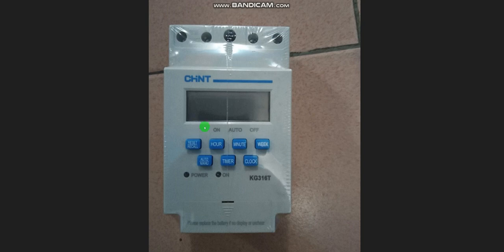It's a calendar timer. You can say, okay, every Monday, this gen can come up. Monday till Friday, gen 1 can work, then another Monday till Friday, another gen can work. Or you can also ration it: one of the gensets can work in the day, and the second genset can work at night. So use this module to interface that particular function.